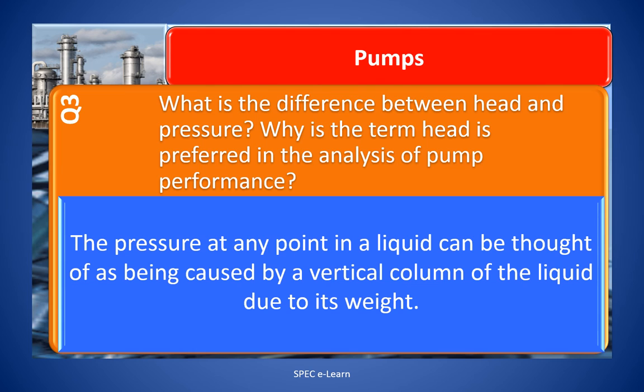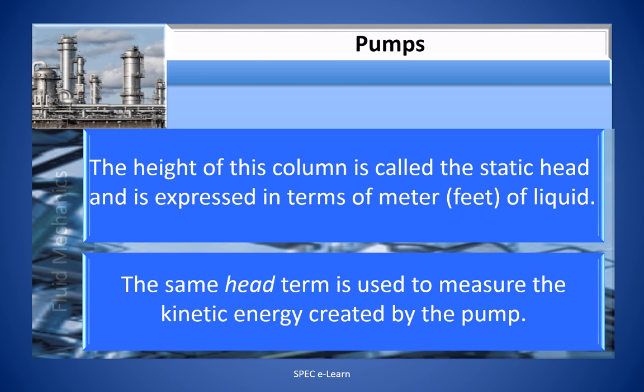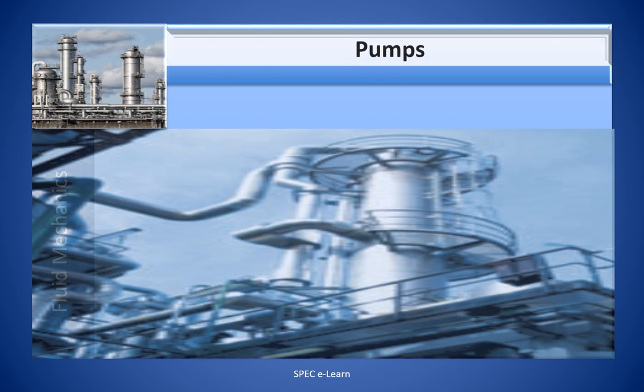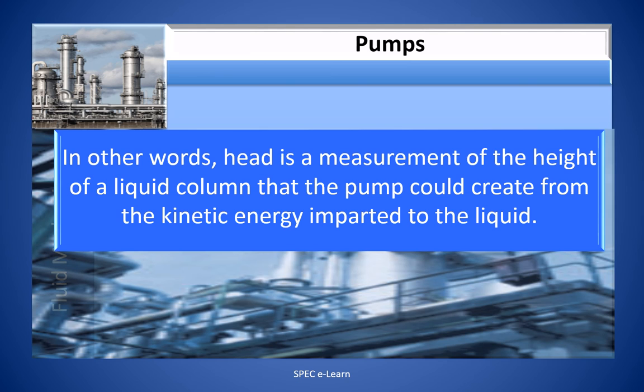The pressure at any point in a liquid can be thought of as being caused by a vertical column of liquid due to its weight. The height of this column is called static head and is expressed in terms of meters of liquid. The same head term is used to measure the kinetic energy created by the pump. In other words, head is a measurement of the height of a liquid column that the pump could create from the kinetic energy imparted to the liquid.